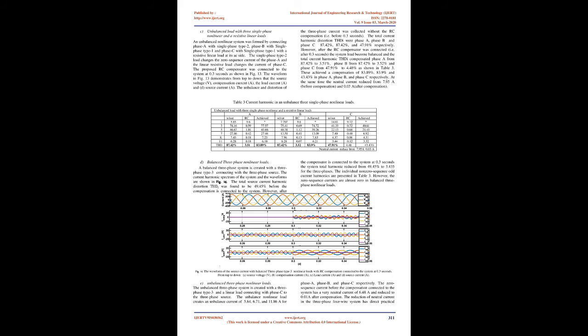Before 0.3 seconds, the total current harmonic distortion THDi were phase A, phase B and phase C 87.42%, 87.42%, and 47.91% respectively. However, after the RC compensator was connected, i.e. after 0.3 seconds, the system load became balanced and the total current harmonic THDi compensated phase A from 87.42% to 3.51%, phase B from 87.42% to 3.52% and phase C from 47.91% to 4.48% as shown in Table 3. These achieved a compensation of 83.89%, 83.9%, and 43.43% in phase A, phase B, and phase C respectively.